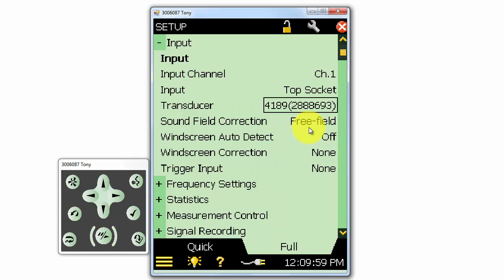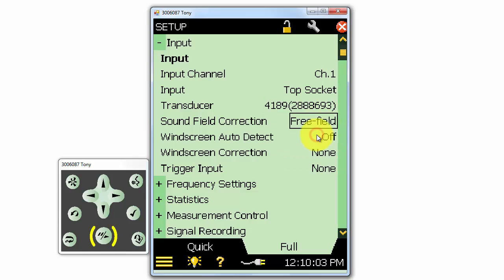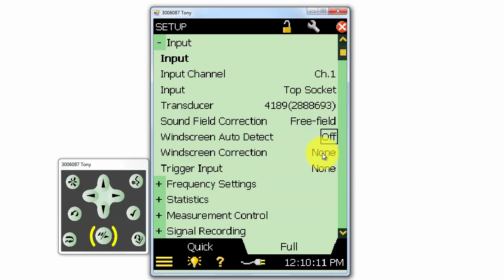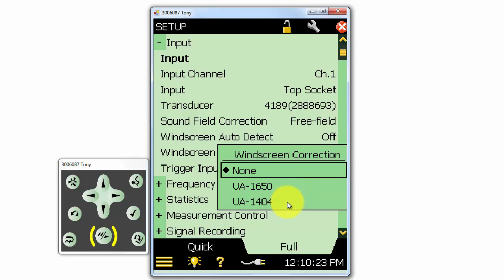We can apply a sound field correction, whether we're in a free field or diffuse field. We can tell the meter to use the automatic windscreen detection. If we're not using the windscreen auto detection, we can manually apply a windscreen correction. The UA1650 is the standard windscreen that comes with the meter. The UA1404 is the outdoor windscreen for permanent or semi-permanent microphone installations.